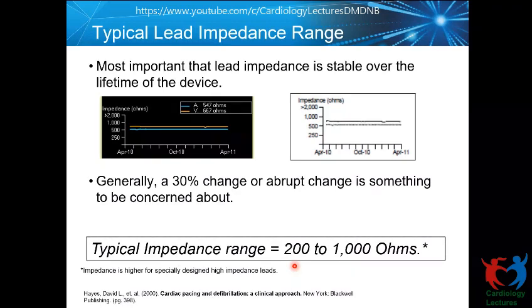A pacemaker patient with a lower impedance from an insulation break may not report a loss of capture, because current is still flowing at the tip. Whereas when the impedance is above 2000, typically when there is a fracture, it happens. And usually it's not even 2000, it's something like 4000, 5000 or upwards of 10,000. That means there is a total fracture between the proximal end of the conductor and the distal end of the conductor, so no current flows through that. And so these patients usually report with a loss of capture and hence symptoms.